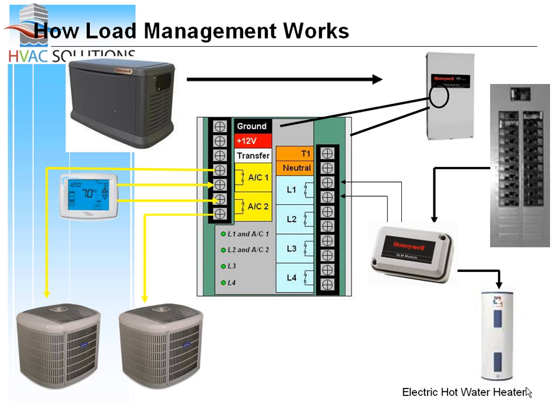If I run through a quick sequence of operation: we lose utility power, the generator at the top left turns on, sends power through the transfer switch, and the first thing that happens is we turn on what I'll call the 115 volt circuits in the customer's circuit breaker box. What are the 115 volt circuits in a house? You get lights, outlets, the fridge, the sump pump, the garage—probably a few more I can't think of at the moment. So you get all the emergency things, or things people need right away.